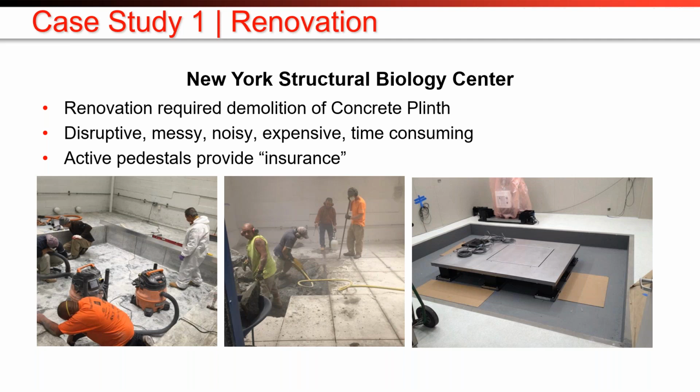You can see the plinth has had the pit dug into it in the image on the right, and you see the two platforms: an outer ring platform rigidly supported to the bottom of the plinth, and an inner isolated one supported on isolators, supporting the core vibration sensitive part of the tool.